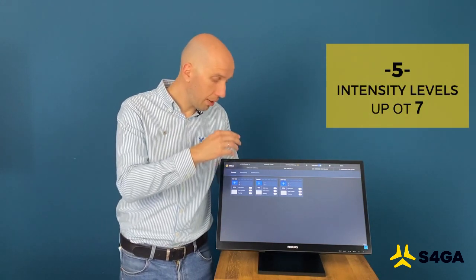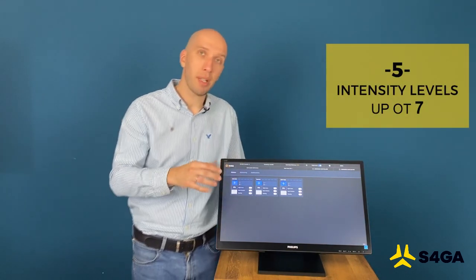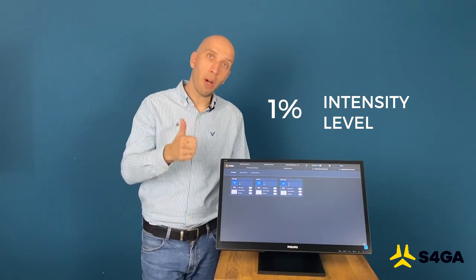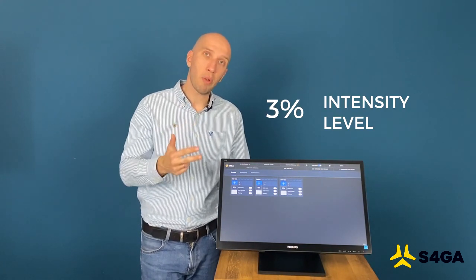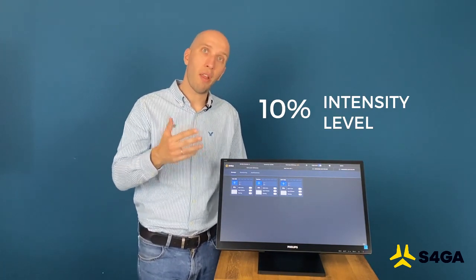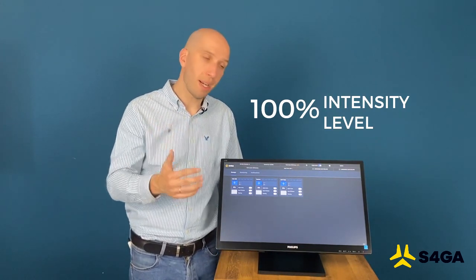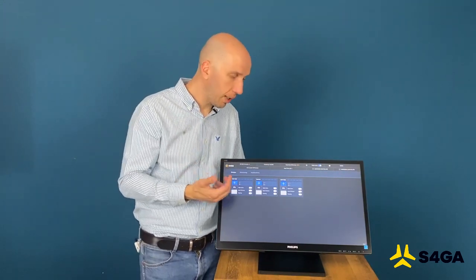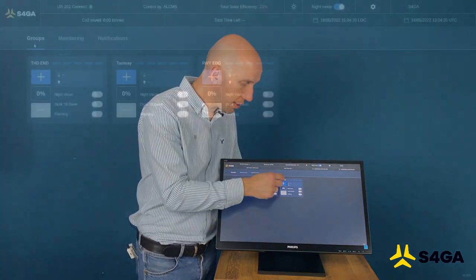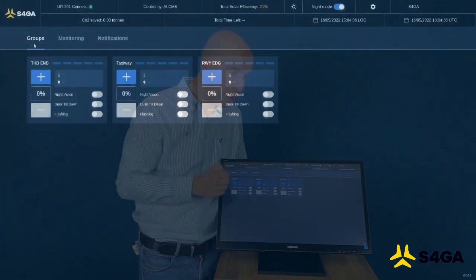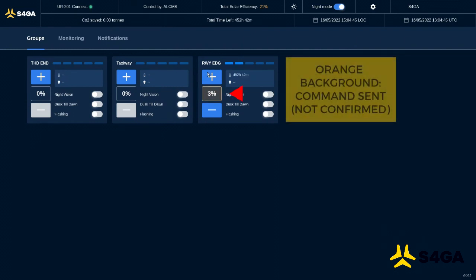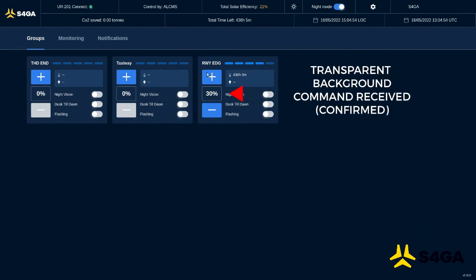So in ALCMS we can adjust intensity in five different levels: one percent, three percent, 10, 30 and 100. So let's see, for example, how can it be done. Let's say I want to activate my runway lighting group on intensity one percent. First, when we select intensity, it is highlighted with orange color. It means that the command is sent but not yet confirmed. As soon as our intensity level changes from orange to transparent, it means the command is delivered to the light itself and confirmed.